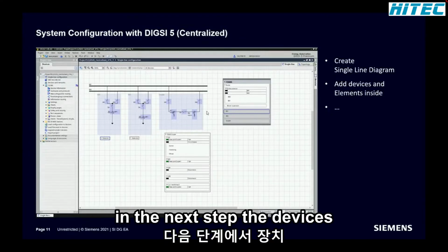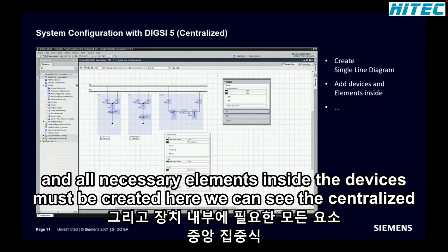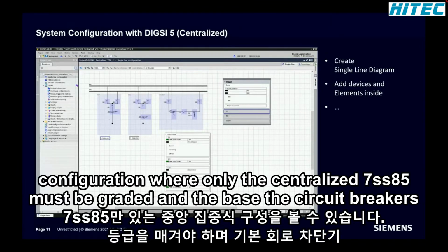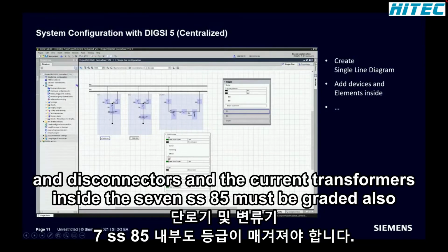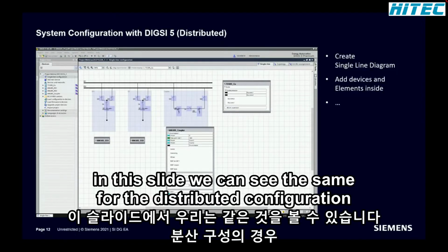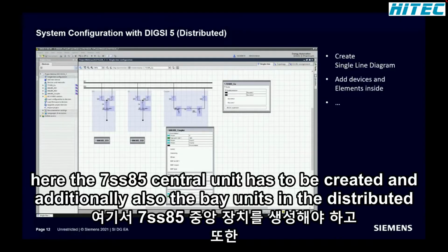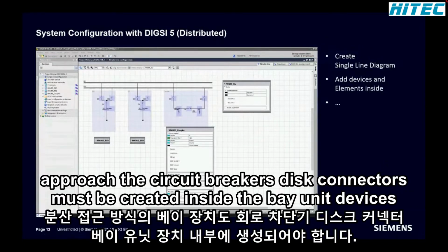In the next step, the devices and all necessary elements inside the devices must be created. Here we can see the centralized configuration, where only the centralized 7SS85 must be created, and the bays, the circuit breakers, disconnectors and the current transformers inside the 7SS85 must be created also. In this slide, we can see the same for the distributed configuration. Here, the 7SS85 central unit has to be created, and additionally also the bay units. In the distributed approach, the circuit breakers and disconnectors must be created inside the bay unit devices.